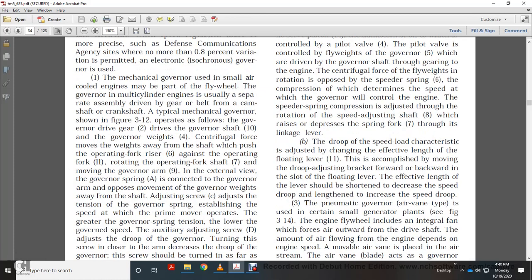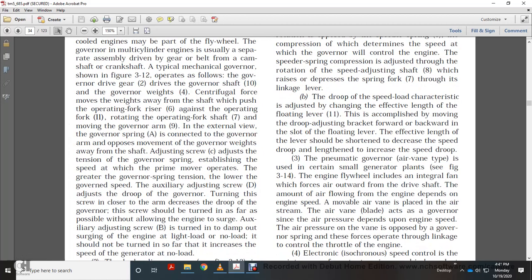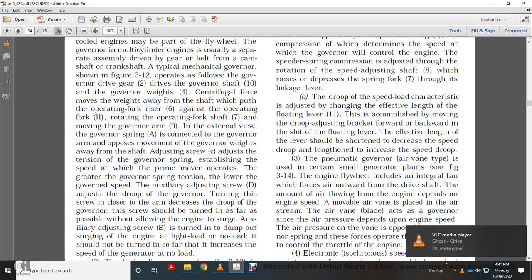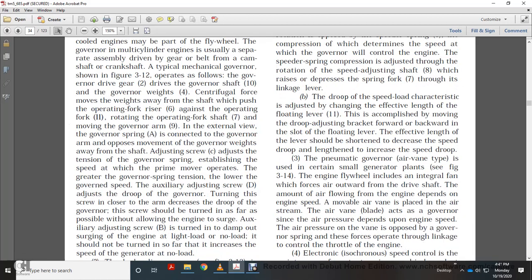Mechanical governing uses a small air-cooled engine and may be deployed with a flywheel. For multi-cylinder engines, the governor is usually a separate assembly driven by gear or belt from the camshaft or crankshaft. The typical mechanical governor operates as follows: the governor drive gear drives the governor shaft. The governor flyweights exert centrifugal force away from the shaft, pushing against the operating fork and rotating the operating fork shaft, moving the governor arm against the external governor spring. The adjusting screw sets tension on the governor spring, establishing primary speed. The auxiliary adjusting screw controls speed droop; turning the screw inward decreases droop, and it should be turned in as far as possible without allowing the engine to surge.